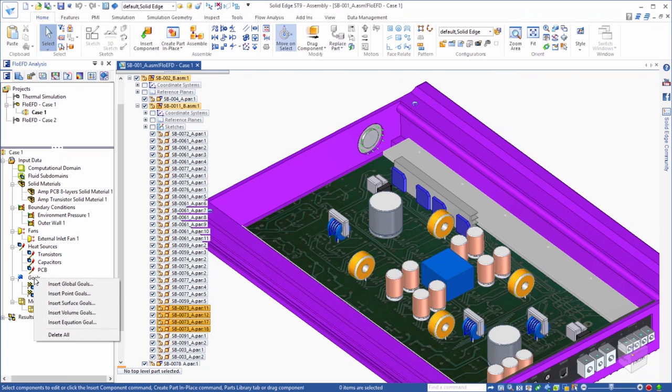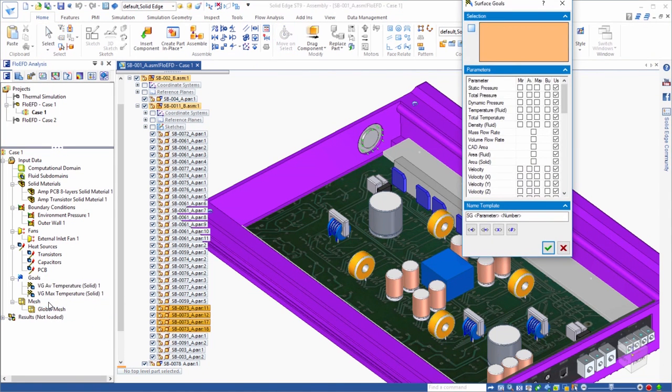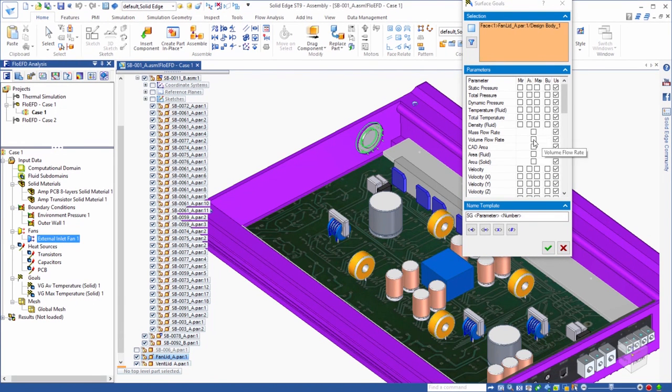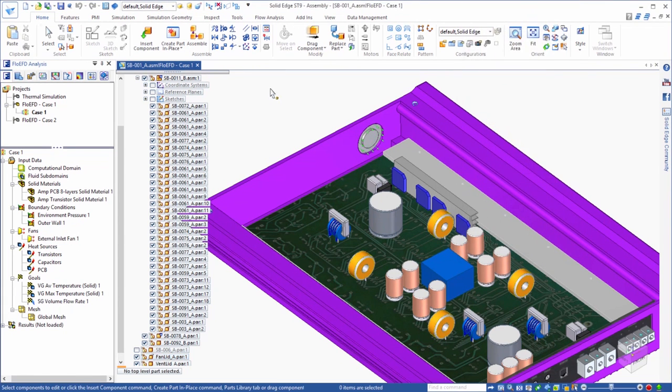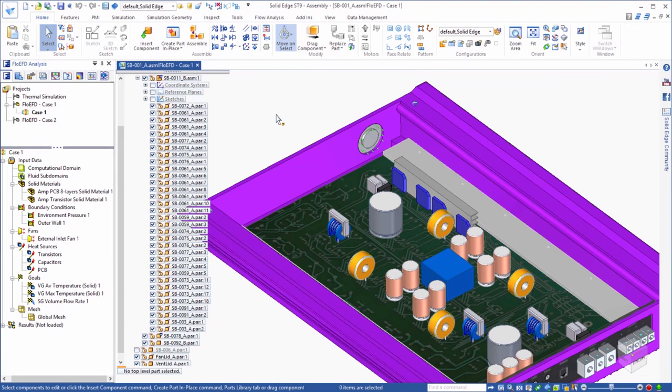Similarly, we want to know, based on the fan curve that we assigned, what the eventual flow rate is that is produced by this fan. So, we can assign a volume flow rate goal to the fan face. The other purpose of goals is to help guide the convergence of the run, meaning that the solver will look for these goals to reach a steady state solution before determining that the solver phase of the analysis is complete.